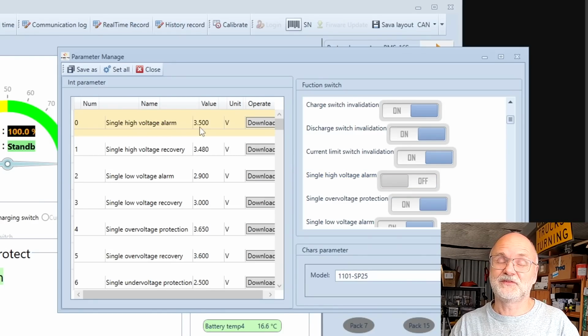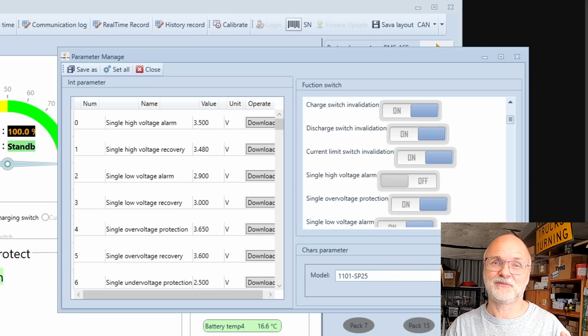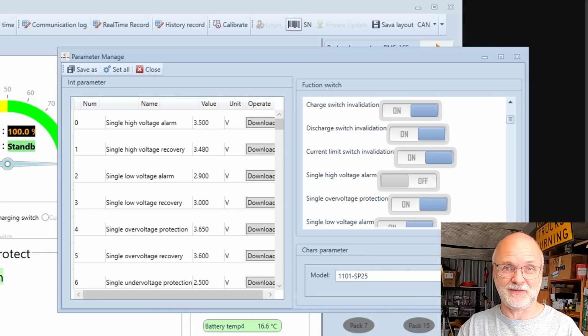Usually at 3.5 volts this alarm comes on and limits your charging current into the battery to 10 amps as well, which some people like because they say it slows down the charging process and gives the BMS and balancer time - though that doesn't actually make a difference.